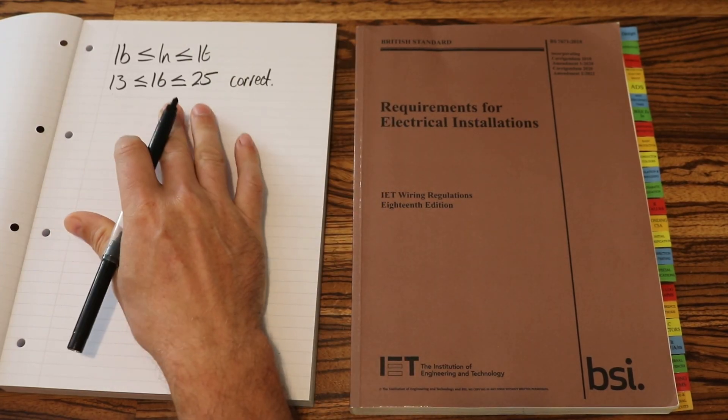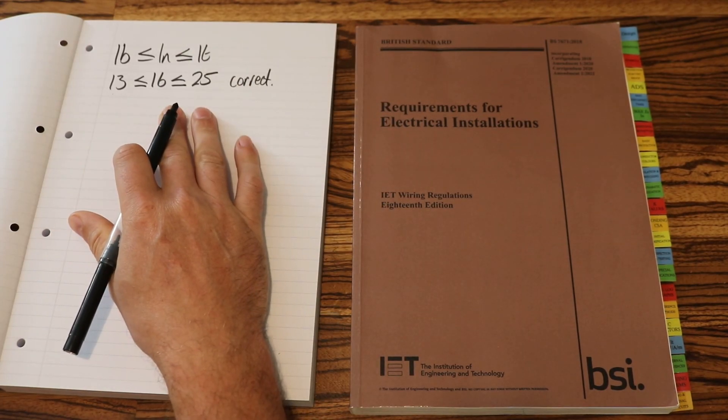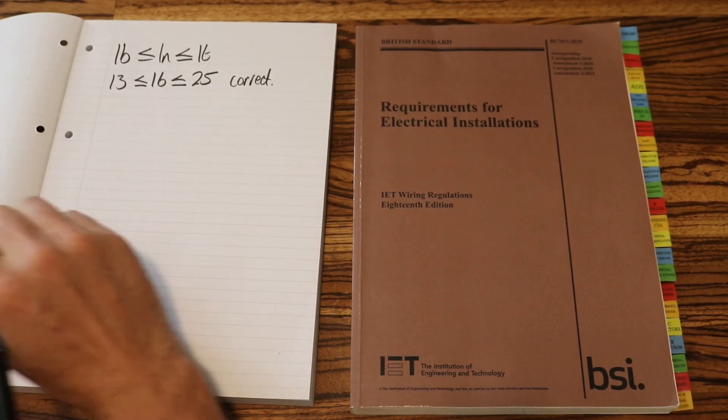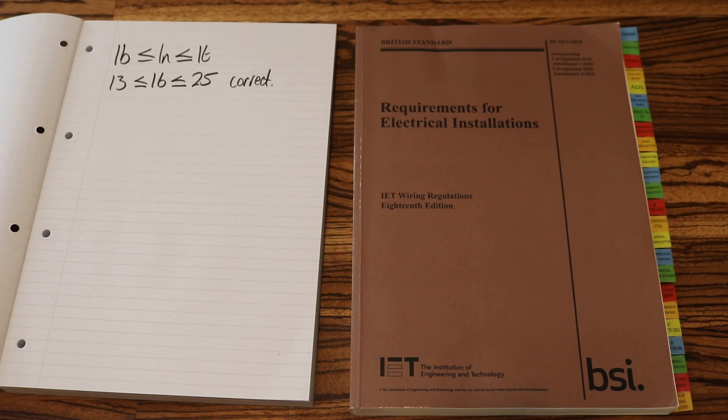And there we have it. So our correct size cable for this question would be 2.5mm. And that is how we do cable calculations just using the BS7671.